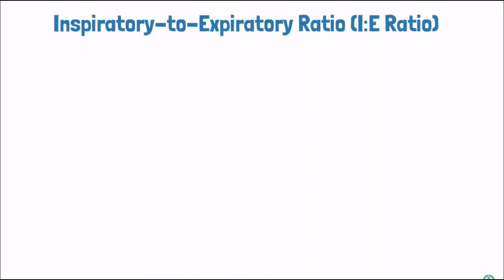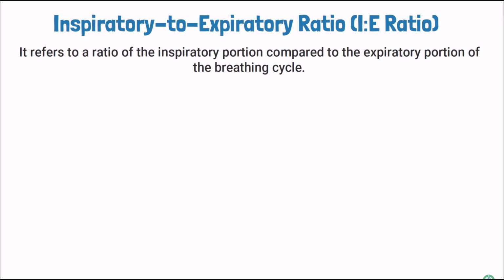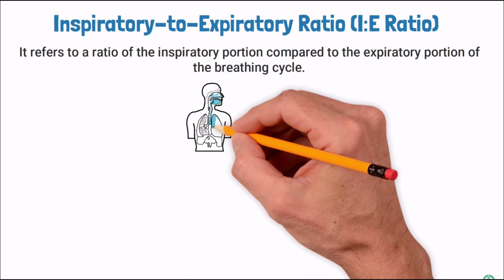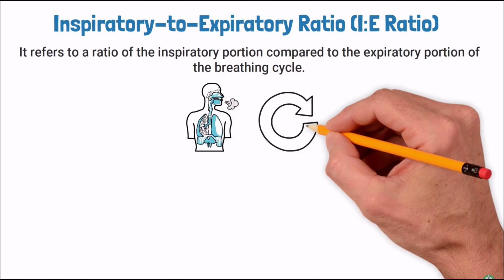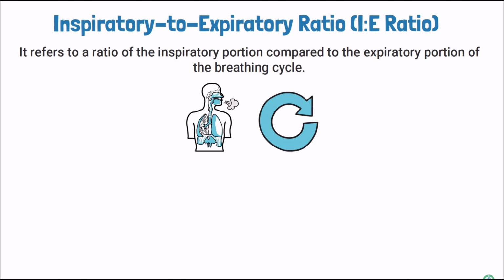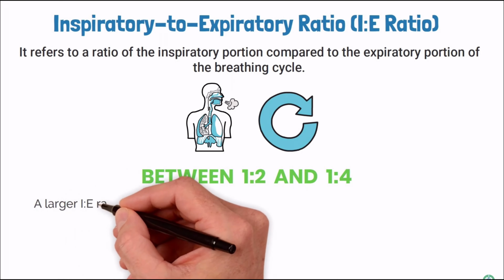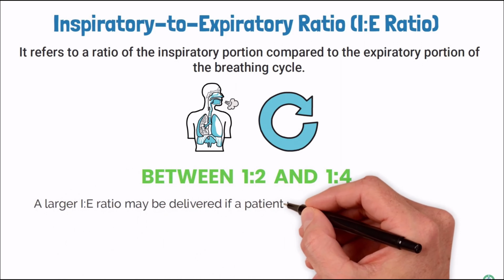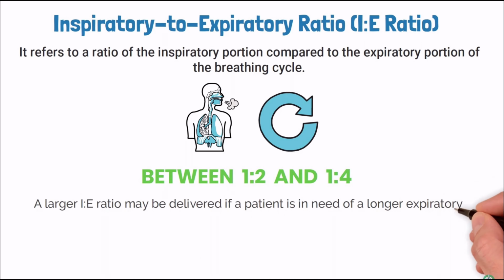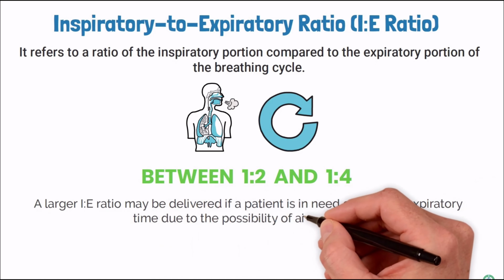An important parameter is the IE ratio. It refers to the ratio of the inspiratory portion compared to the expiratory portion of the breathing cycle. The normal IE ratio is between 1 to 2 and 1 to 4. A larger ratio may be delivered if a patient needs a longer expiratory time due to the possibility of air trapping.